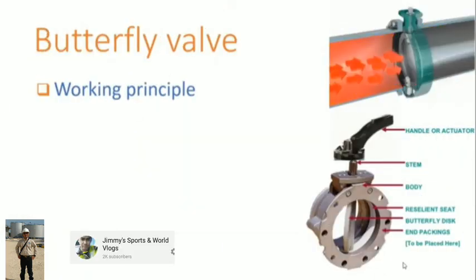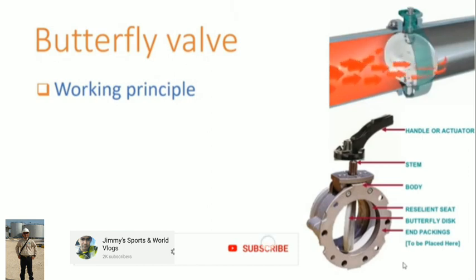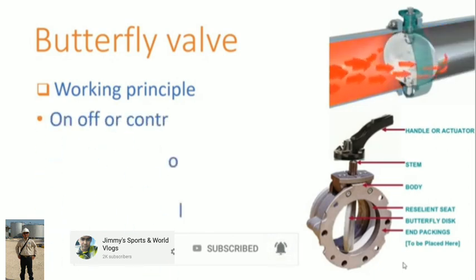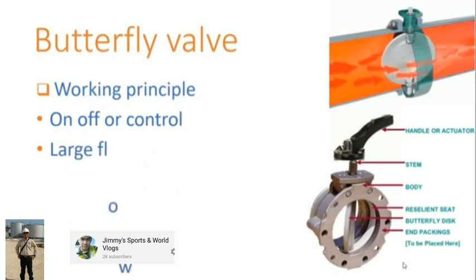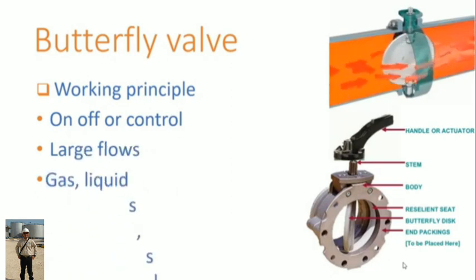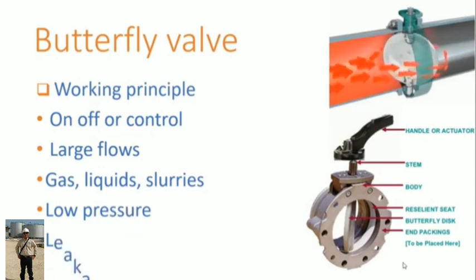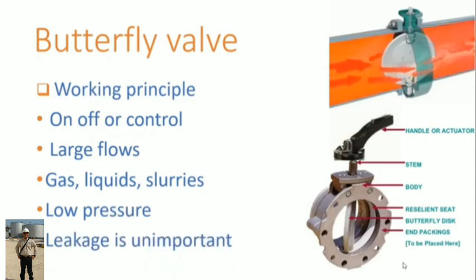Working principle of butterfly valve. This valve has a rotating disc in the pipe section body where a stem passes through. The disc is supported by both ends of the body. This can be used for both on-off or control applications while handling large flow of gases or liquids, including slurries. Butterfly valve uses for low pressure applications where leakage is unimportant.